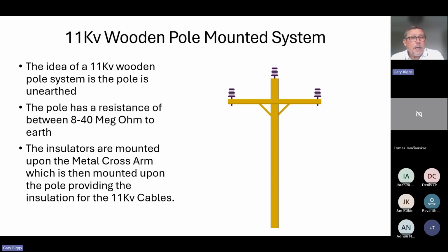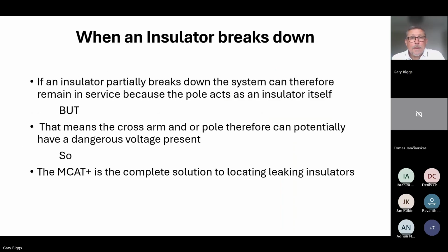So the whole point of this unit is when somebody is working on the poles, they need to know, is that cross member live? And if it is, what level of danger that presents. And that's what this unit will do. So, as I said, the insulator itself can break down and the system can remain in service because the pole itself acts as an additional insulator. But it does mean the cross arm and the pole can have potential voltage, and therefore pose a problem for the person working upon the systems. And so the MCAT itself is our solution to locating leaky insulators on such systems.